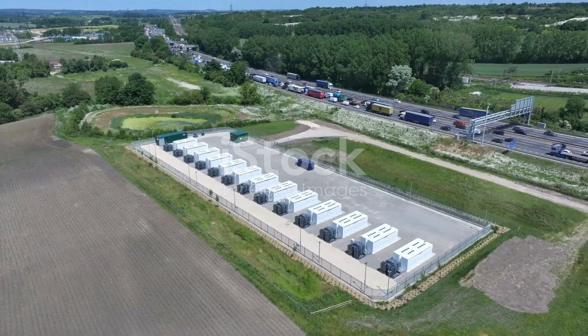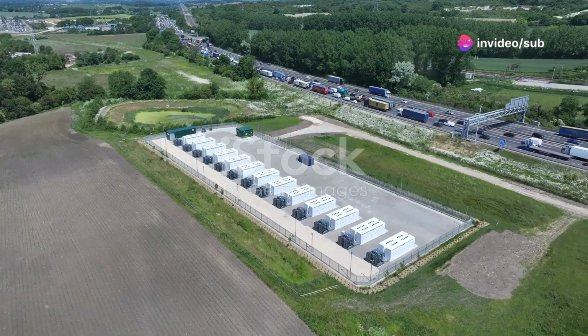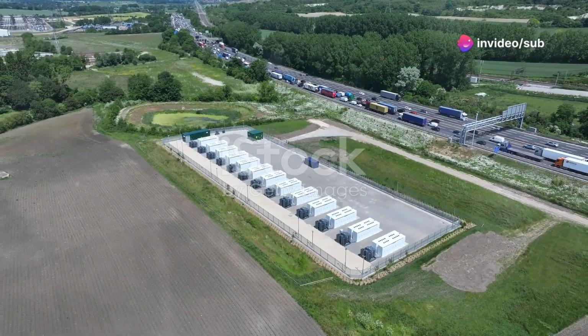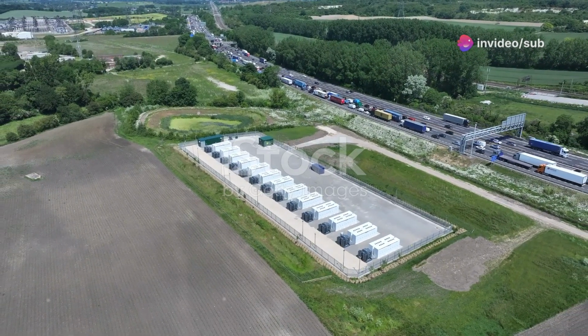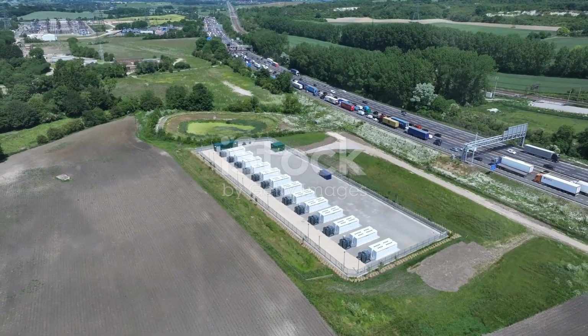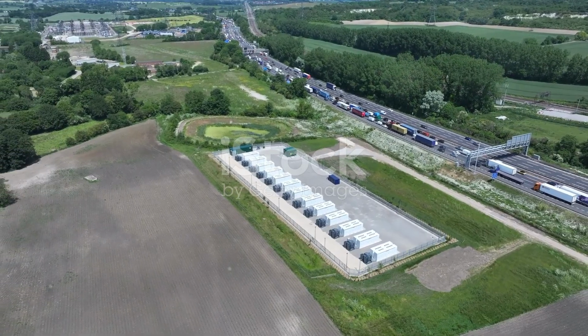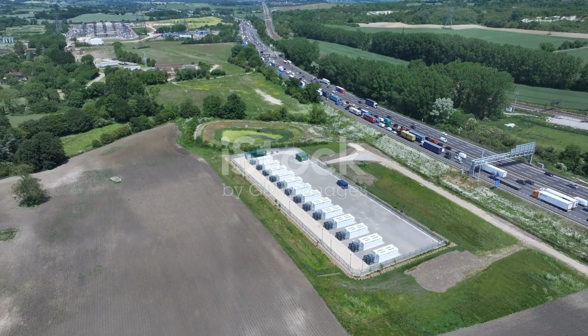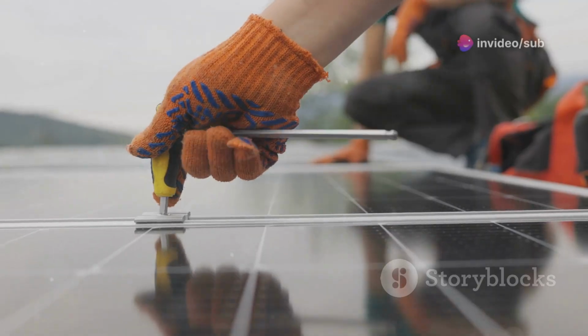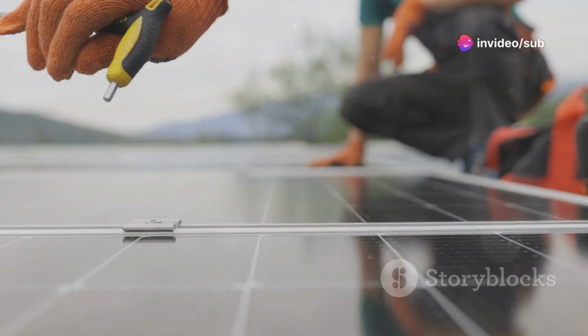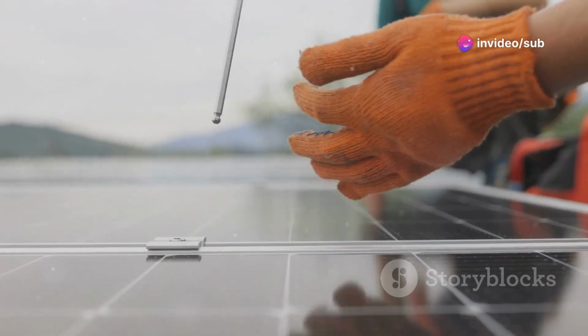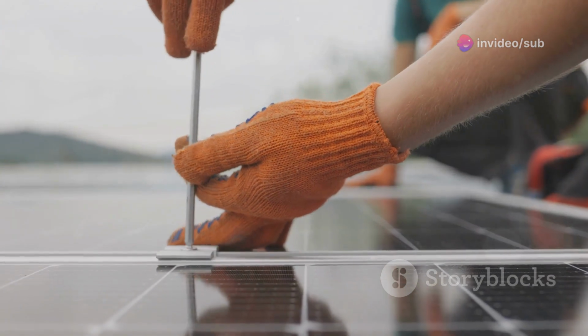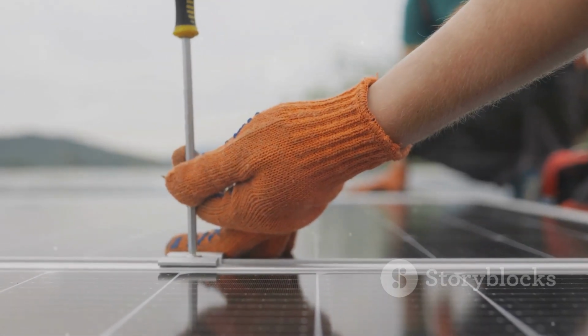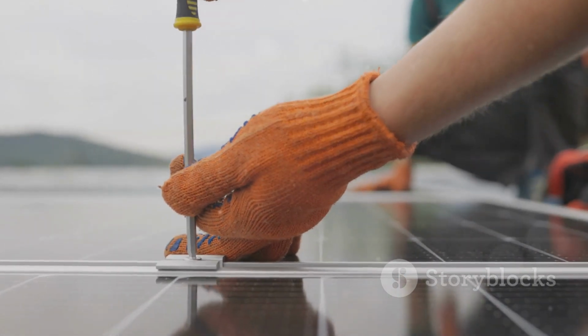You'll need lithium or deep-cycle batteries with enough storage to meet your needs. For a 10-kilowatt system, plan for at least 10 to 20 kilowatt-hours of battery capacity, depending on how much backup power you want. More capacity means longer backup during outages. Fourth, mounting racks and rails. These must be strong, weatherproof, and suitable for your roof type or ground installation. Proper mounting hardware ensures your panels stay secure and optimally angled for sunlight.